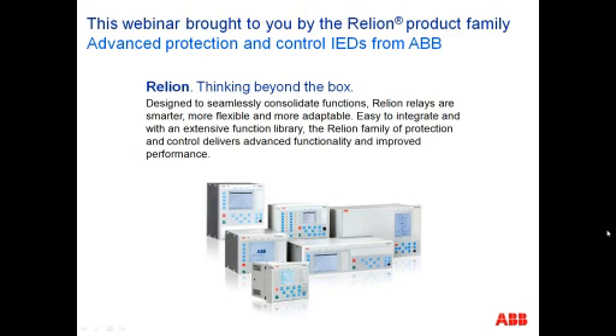and I guess the root of it is a transformer with a delta winding. And of course, there is a circulating current in the delta winding during a fault condition, and also in the non-loaded condition. You have, let's say, a high winding and a low winding, and you have the delta winding. In that fault condition, the difference between the high winding and the low winding is what's flowing in the delta winding, and that is the polarizing quantity.